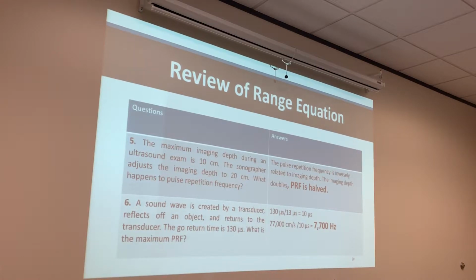Okay. So sound travels again, guys, 1 centimeter for every 13 microseconds. The 13 microseconds is like a total, right? Yeah, it's the go and return. It's the time of flight. Absolutely. And we can determine our reflector depth by applying the 13 microseconds.